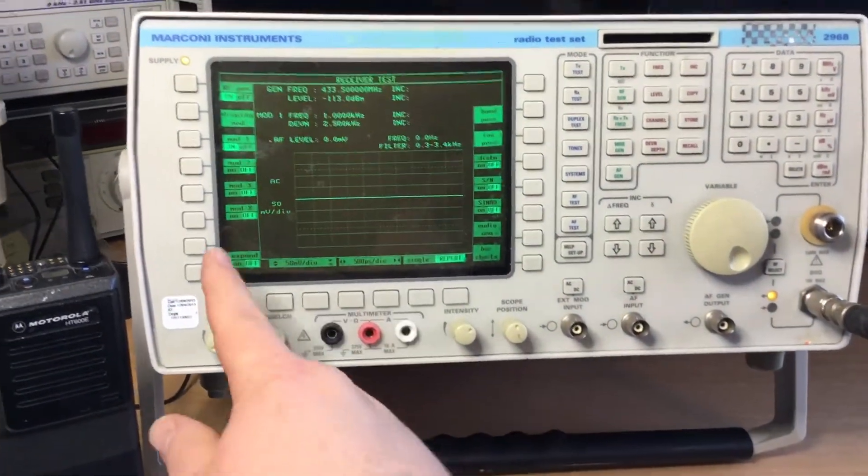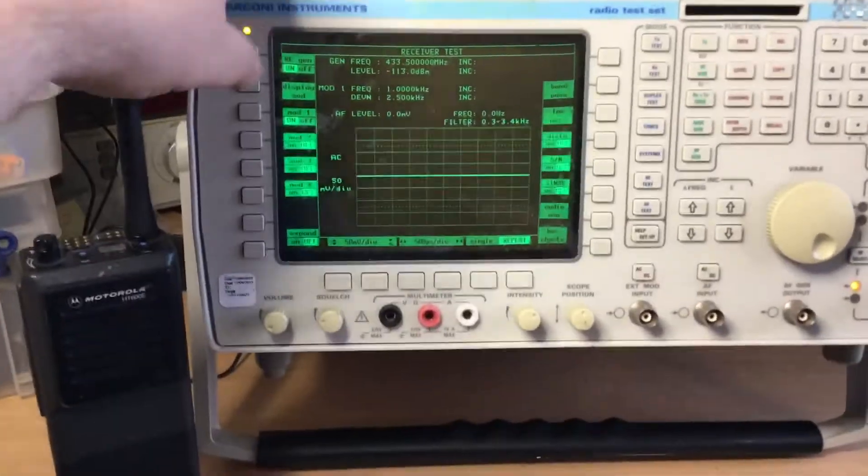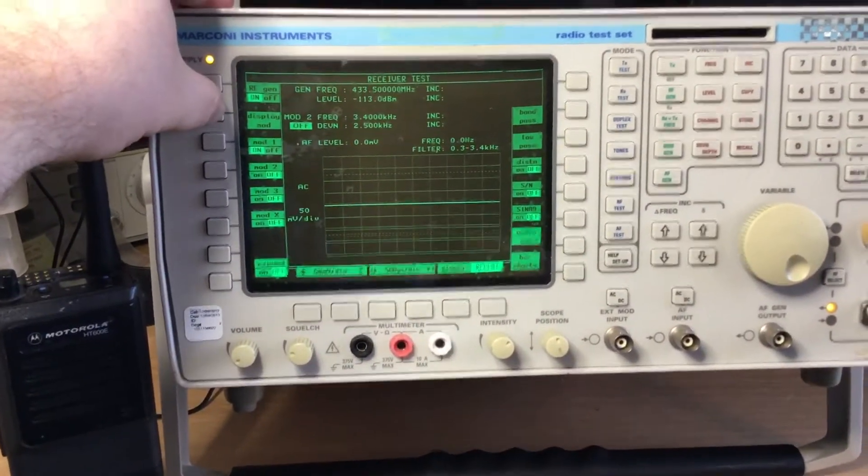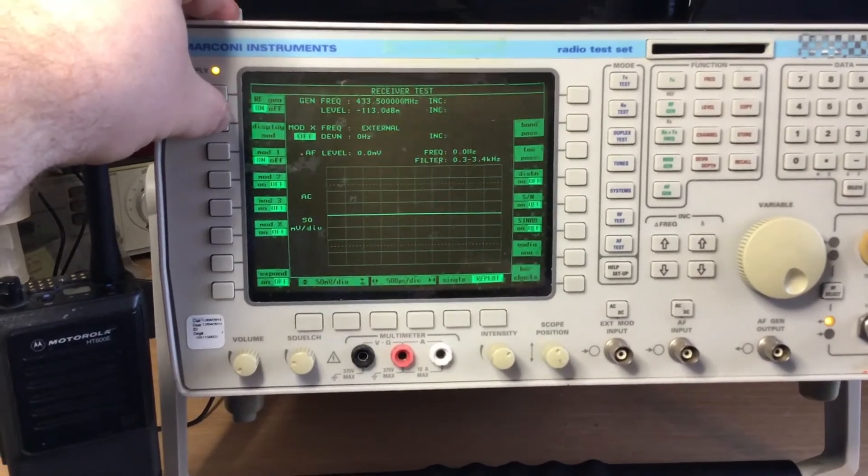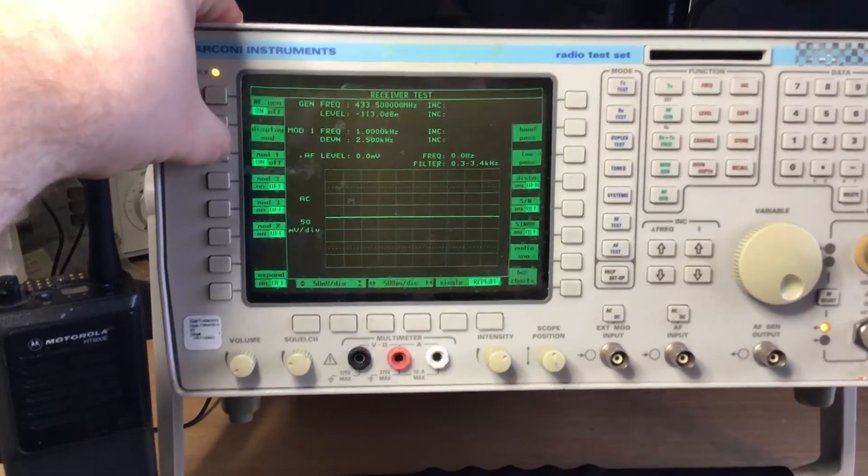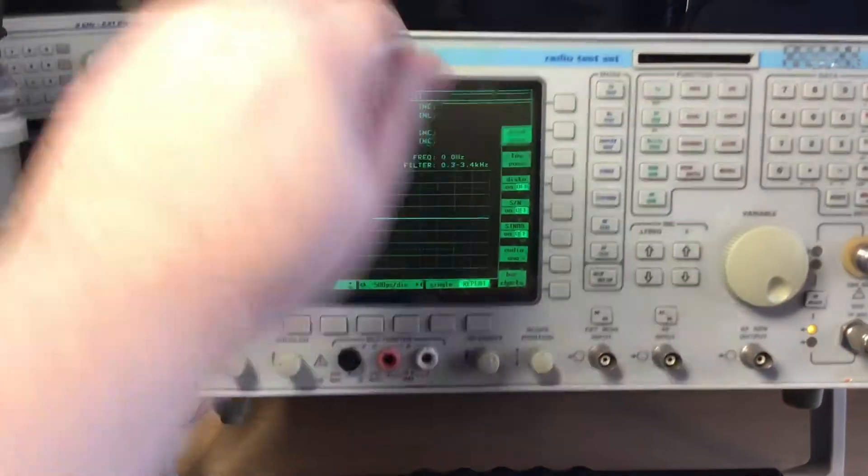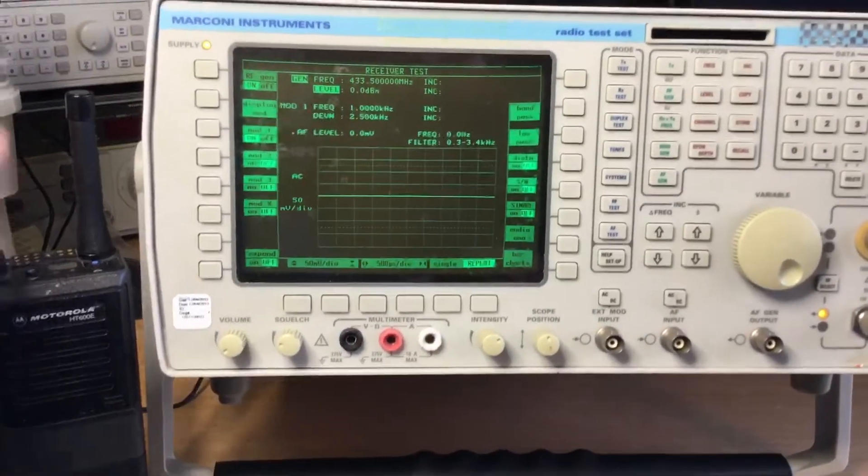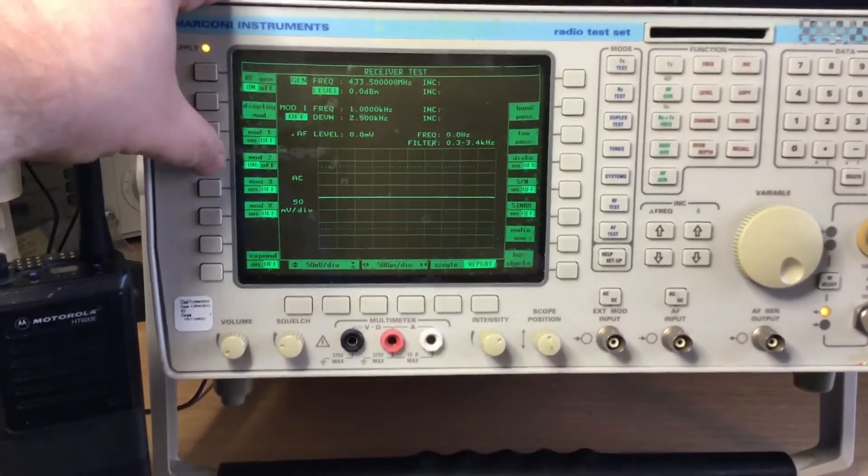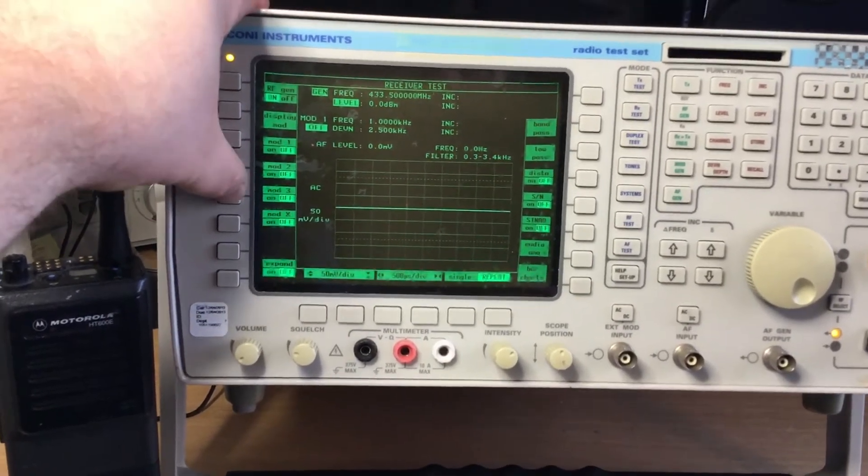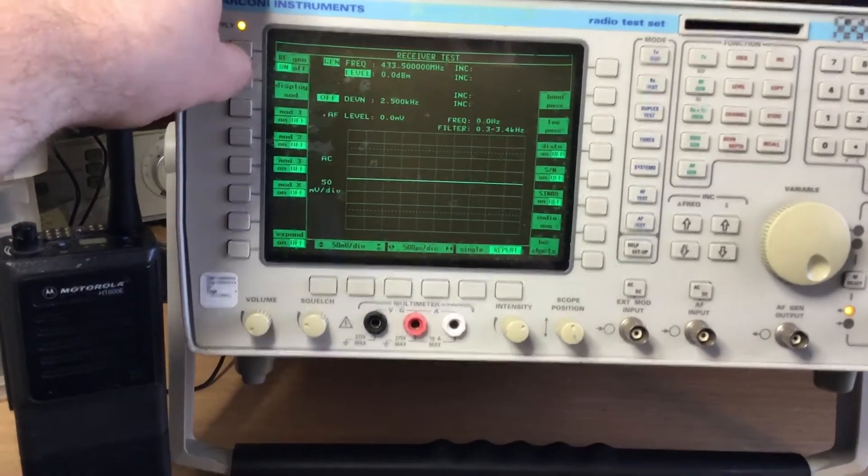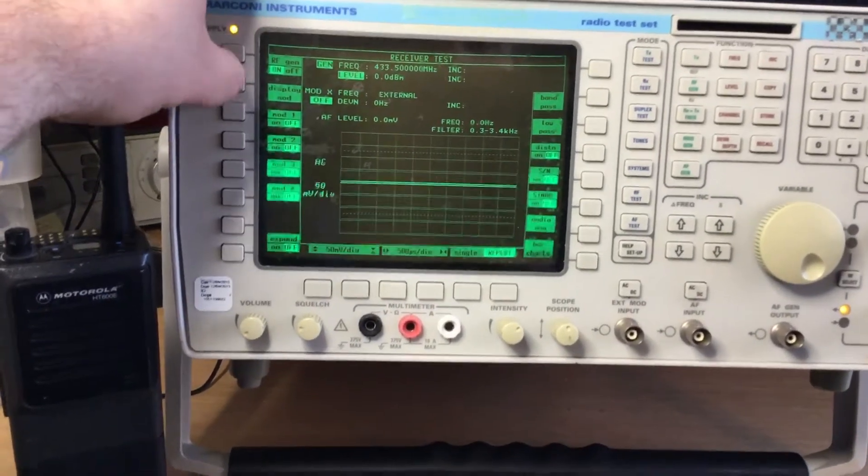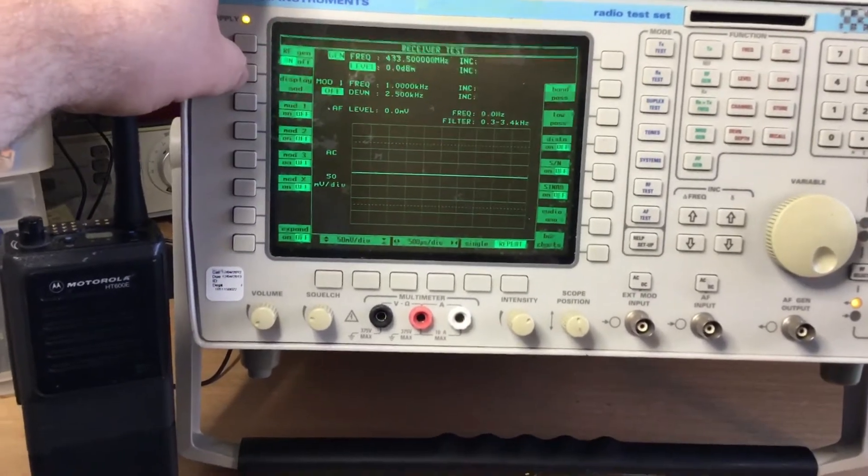We have lots of features in here that we can use. We've got the modulation - our mod gens - so we can, for example, have three mod gens plus an external mod gen if we want. We can set these on and off as appropriate. If I put that back at zero dBm again, we can switch the mod gens on and off. That one's set at 2.5 kilohertz, 500 hertz, etc. We can basically go through each mod gen and set it internally within the test instrument as well.